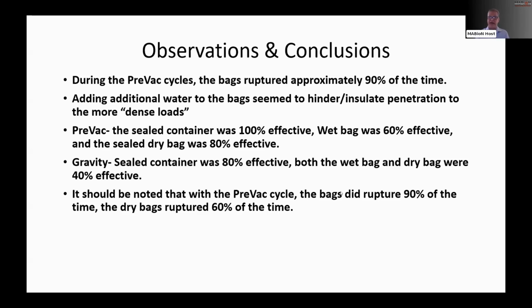It should be noted that the pre-vac bags ruptured 90% of the time. The dry bags only ruptured about 60%. The wet bags are going to produce steam at some point, but the question is where does it do it? Does it do it in the pre-vac? Probably not. That's probably why you're getting a lot of failure. During the pre-vac, the water is not able to get the steam penetration. Remember, steam's going to go after that water because it's cooler. Because it's in a sealed bag, no steam can actually penetrate.